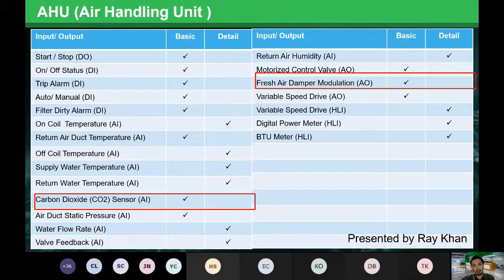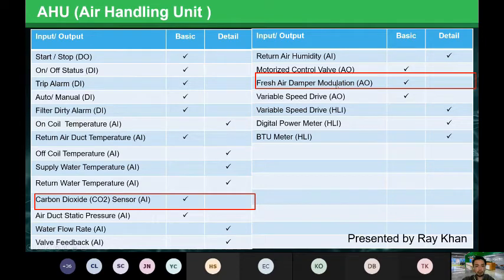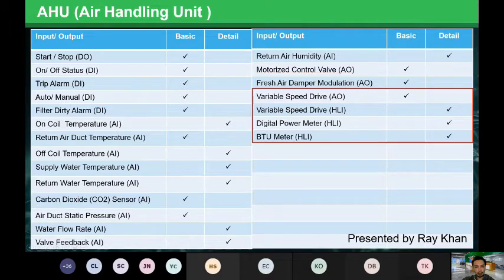Carbon dioxide sensing is commonly deployed for indoor air quality in indoor premises. CO2 sensing is tied closely with the fresh air damper modulation — if the CO2 level is high, the fresh air damper will open up to bring in fresh air. So CO2 sensing is for indoor air quality and is tied closely with the fresh air damper. The output is used to modulate the damper.